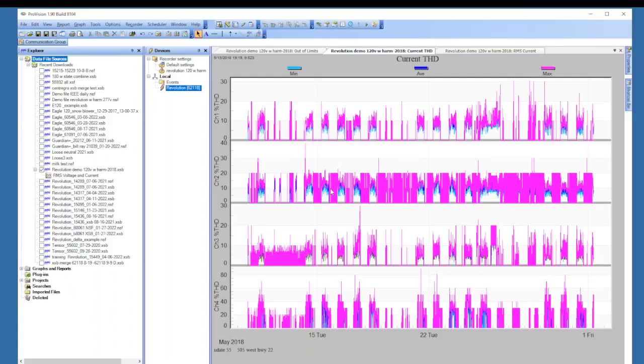Usually what you'll find is the lower the current, the higher the THD is. So it's really not that big a deal if you have 4 or 5 amps and 400% ITHD. The problem comes in when you have several hundred amps and a few hundred ITHD percentage. Then you're starting to run into problems. So you have to look at your ITHD, and you have to look at your current, and you have to really look at when it occurred. Did it occur when there really wasn't much current there, or did the high ITHD occur all the time? So you do need to do more. Nothing really cut and dry there.